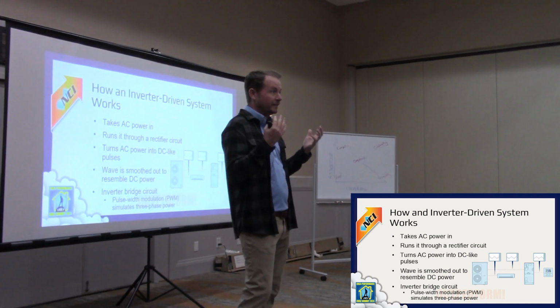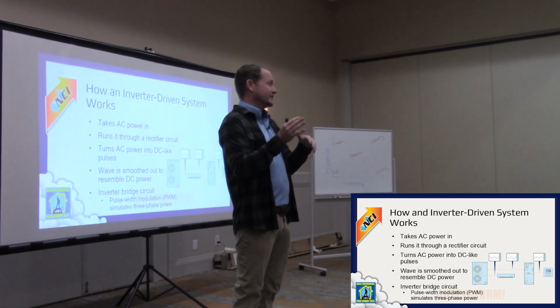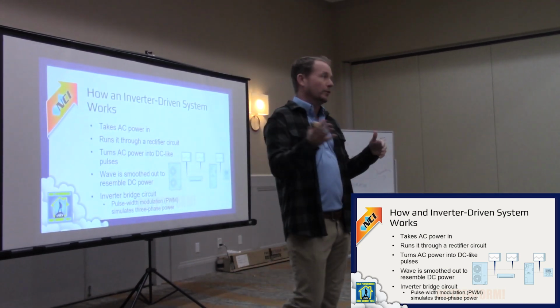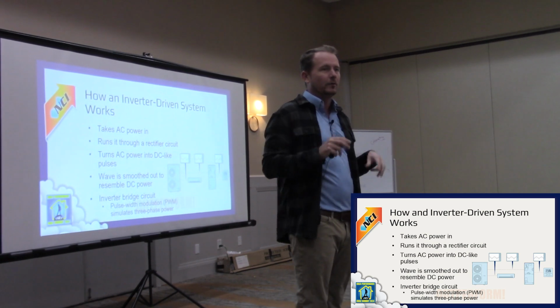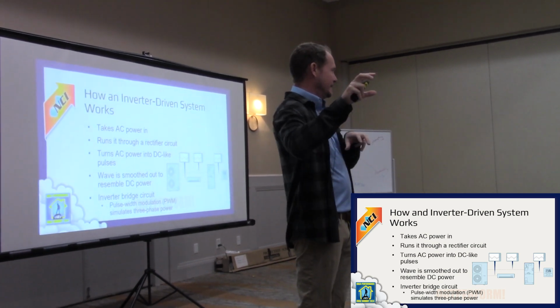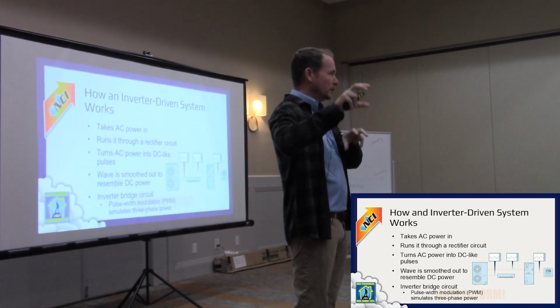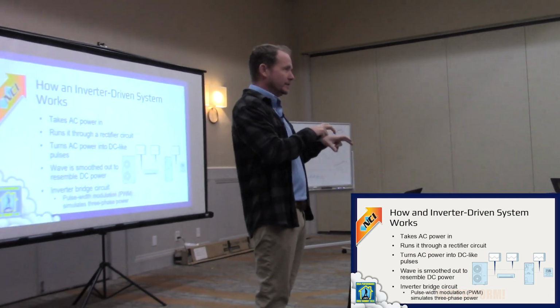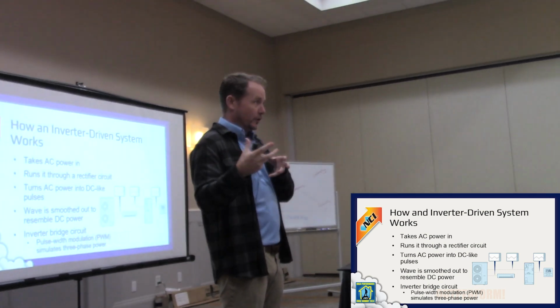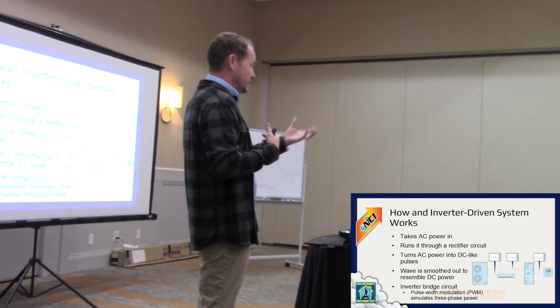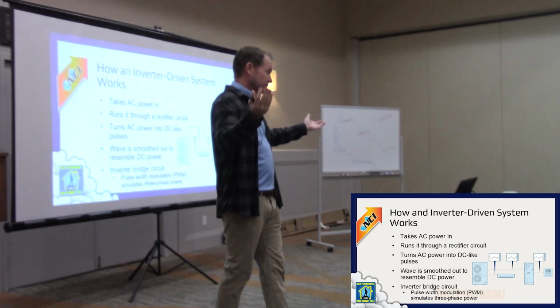Now, when we're talking about inverter-driven equipment, we're not generally referring to an ECM blower, but an ECM blower is an inverter-driven motor. That's what it is. It has an inverter, a drive on the back of it that controls the speed of that motor at varied frequencies. Everybody get that?